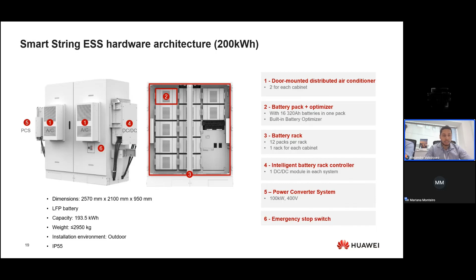To go a little bit more into the components, here we can see the battery pack. It is lithium iron phosphate, the material, and has a rated voltage of 57 volts. Each one of them has a 16 kilowatt hour capacity and weighs under 140 kilograms. And the smart PCS is 100 kilowatt, so the battery has a capacity of 200 kilowatt hour.